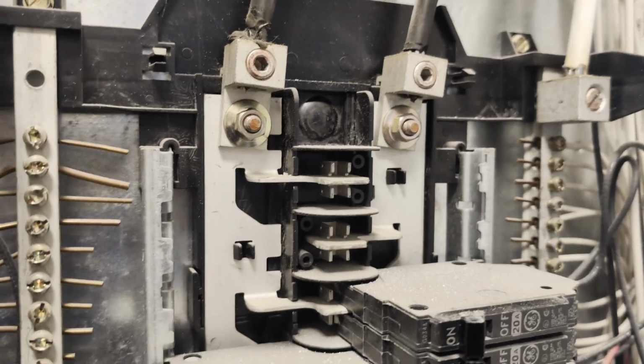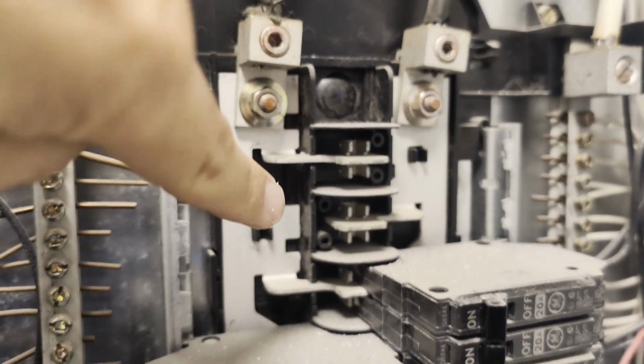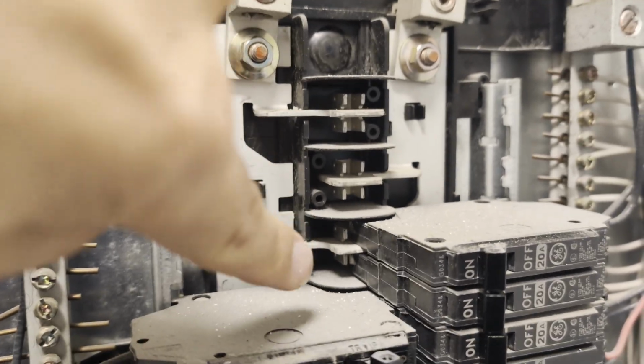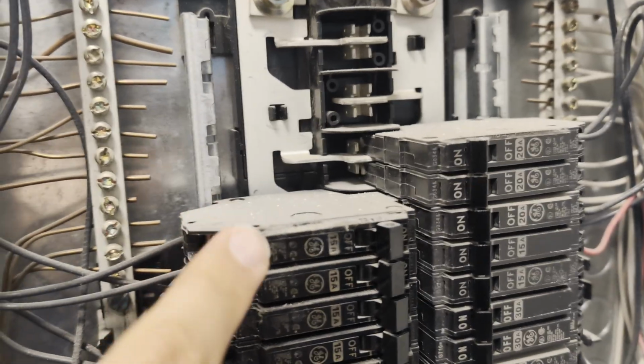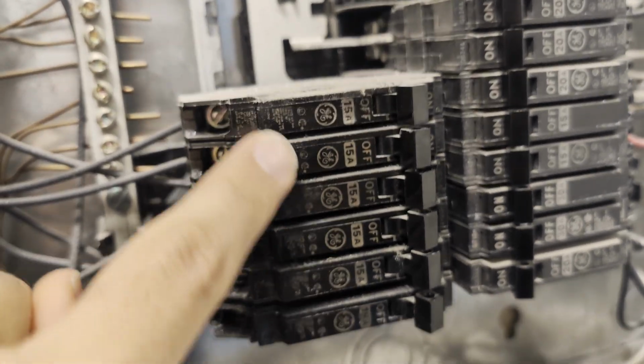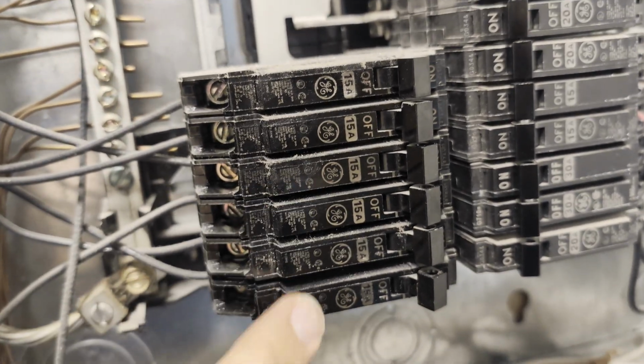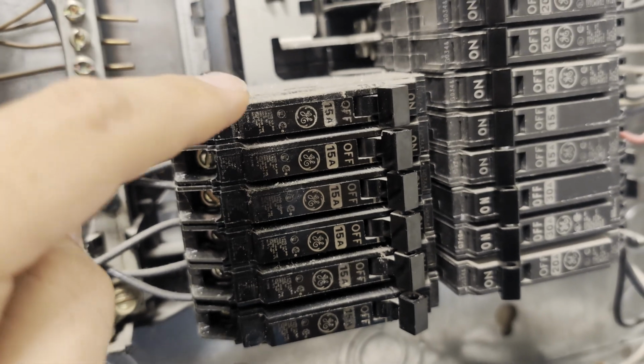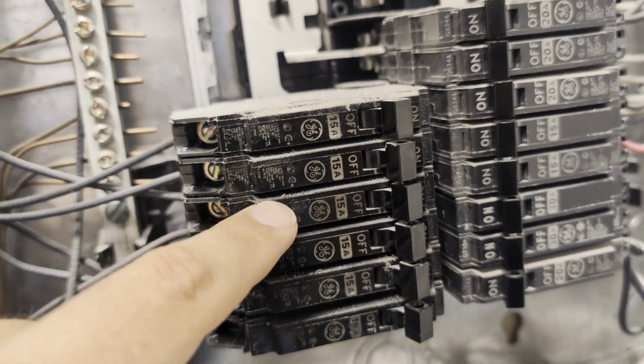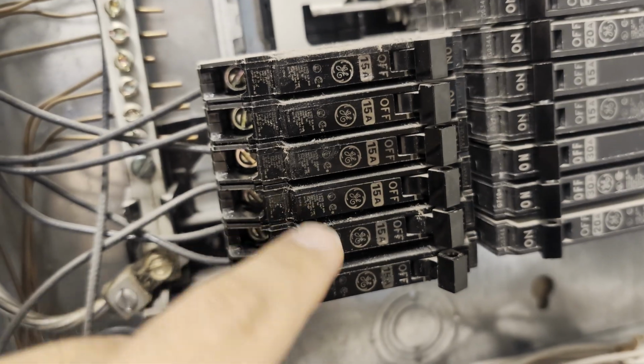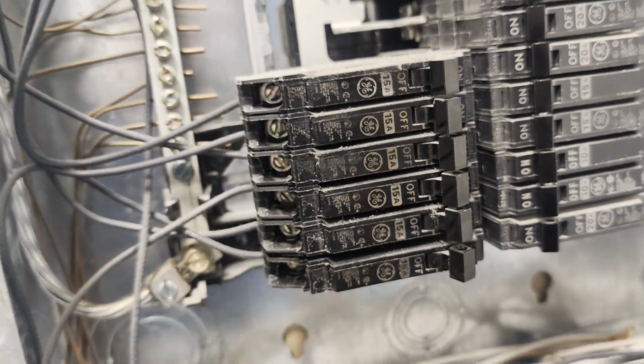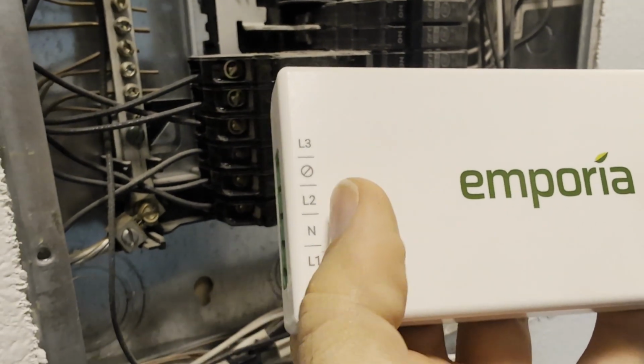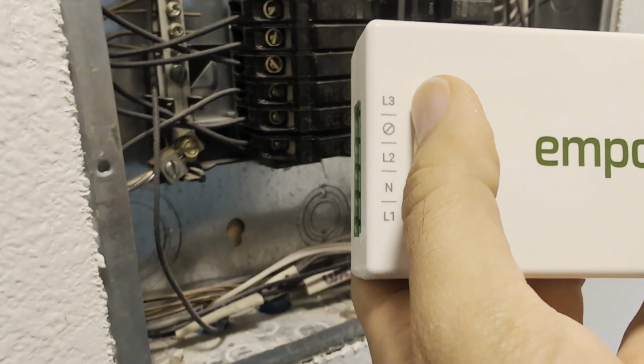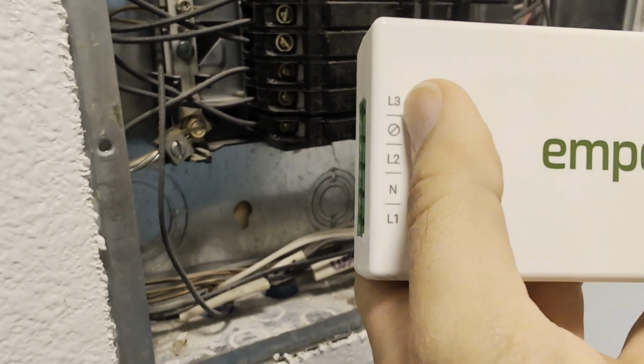The two hot lines are shared among the two vertical arrays of breakers. The first two breakers are connected to the left hot line, and the two under that are connected to the right hot line, and it flip-flops back and forth like that. It's important to know this, since we need to pull one line of power from each hot line. We will connect these two hot lines to the L1 and L2 ports.